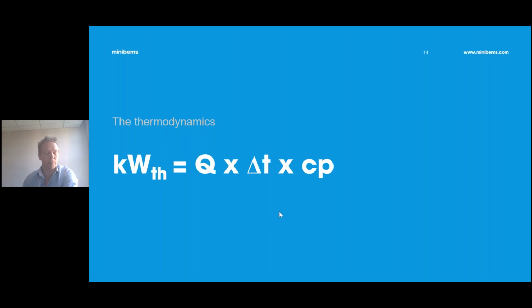So just to summarise really what Ben was saying, essentially we do see most heat networks in the UK running at anywhere from sort of 25% up to 50% efficiency. We don't see a lot of heat networks, where we've done heat network studies for clients, where the performance is above that. In a lot of cases, it's simply that pretty much all heat networks today in the UK anyway don't have any real-time optimization on the demand side of the network. All the control tends to be in the plant room or the energy center. But of course, the thing that is controlling flow rate is not in the energy center, and I'm going to go into that in a bit more detail.